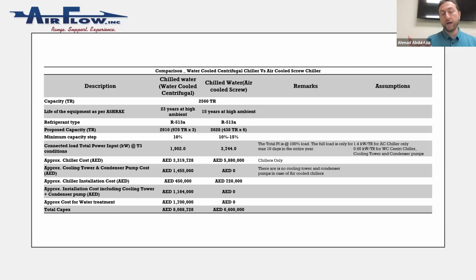Then the part load, when you go down, is 15%, 10% for air cooled and 10% for water cooled. So it's almost near to each other. Now the connected load, this is based on T3 conditions at AHRI. So you will have 1,902 kW from water cooled and 3,744 kW from air cooled. Based on the rates in Dubai, the cost for the first system, the water cooled, is 3.3 million dirhams, the local currency. I think 3.7 dirhams equals $1 in that range. So you'll get more like $1 million, maybe, for the first system. The second system, air cooled, is 5.8 million dirhams, like 1 point something million dollars.